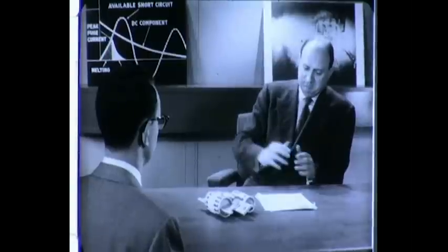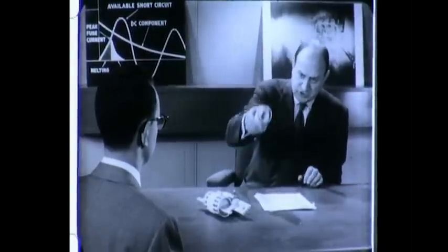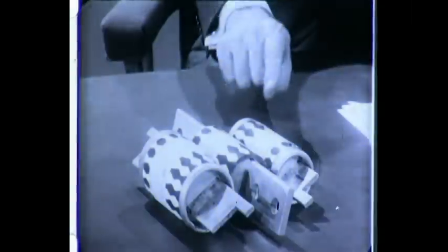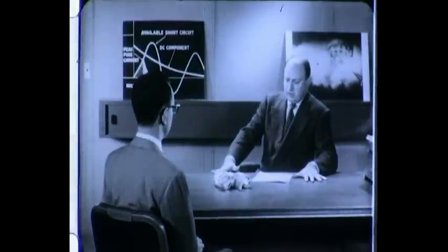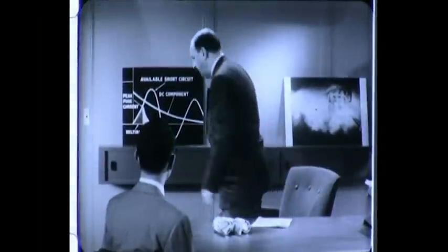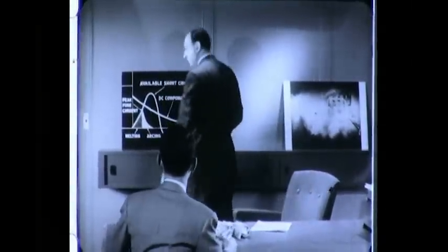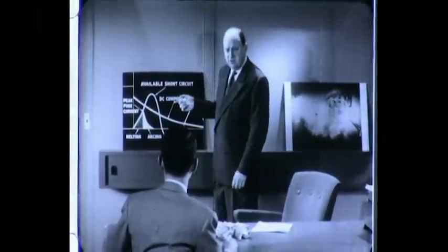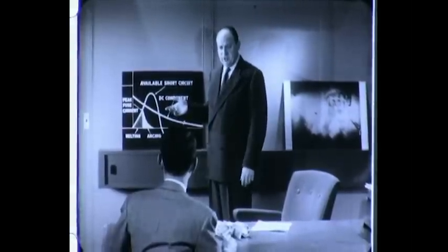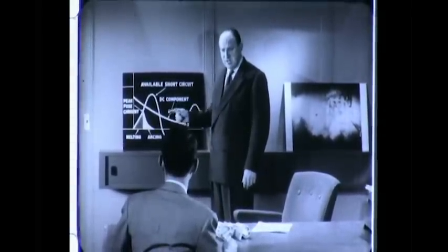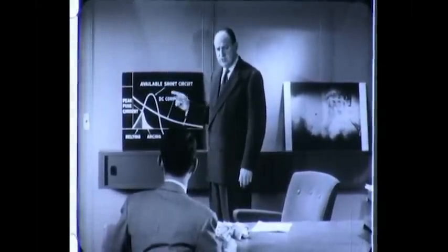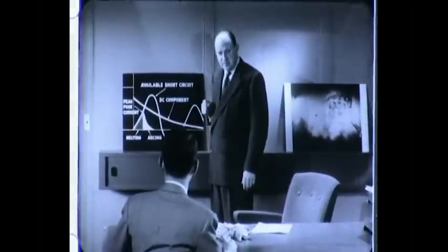And now that you have joined our sales force, Cruncher, I'm going to teach you some of the finer points of selling. Do you know what this is, Cruncher? This is a current limiting fuse, my boy. And do you know what it does? The current limiting fuse is designed to limit the amount of short circuit current that can be developed on a circuit. An ordinary fuse can only operate successfully in circuits up to 10,000 amps. Now this CLF can interrupt a short circuit up to 200,000 amps.